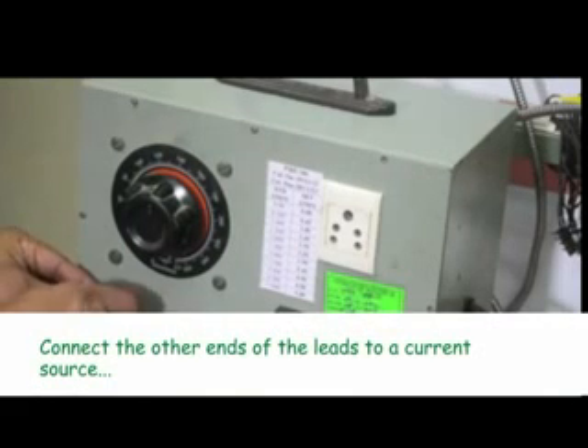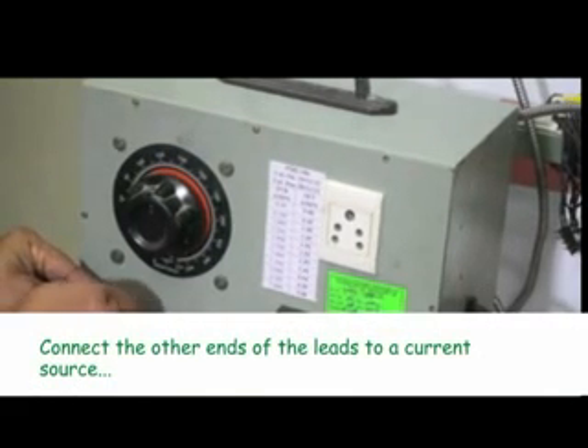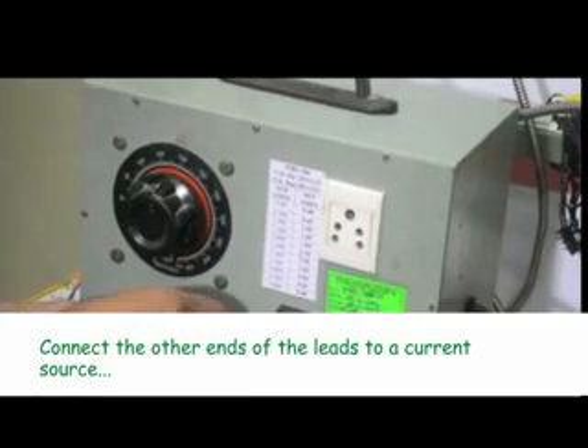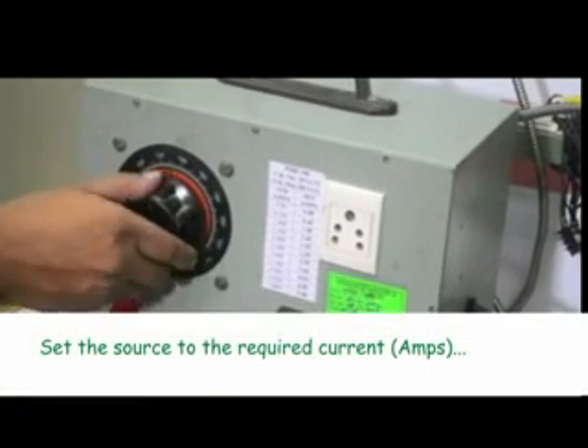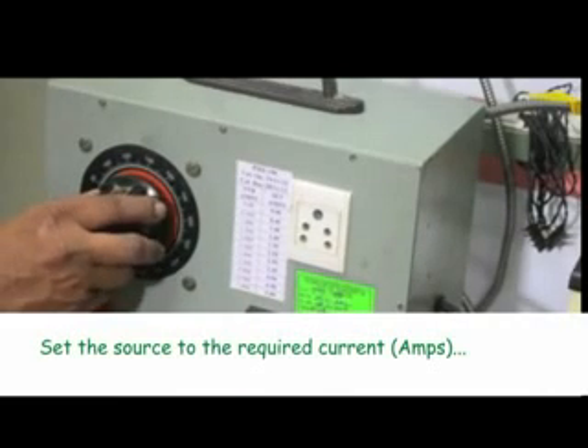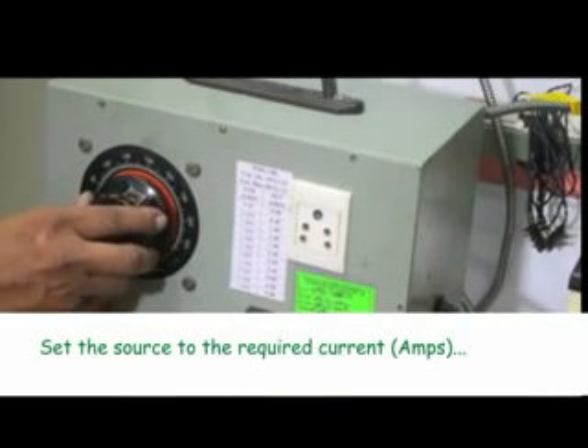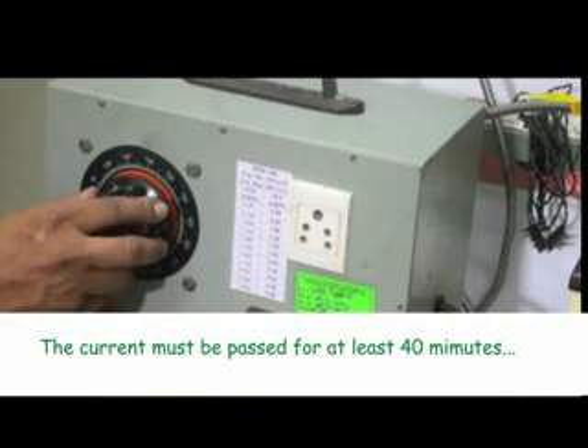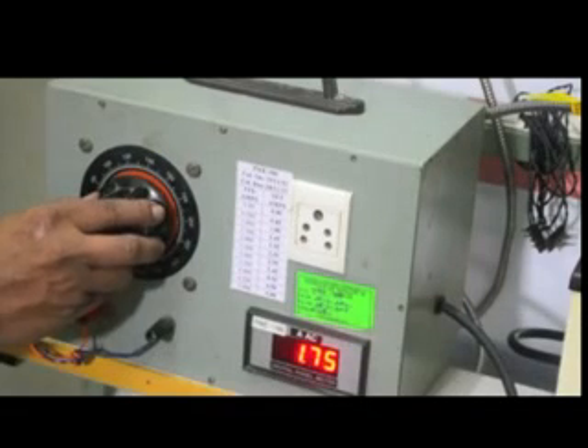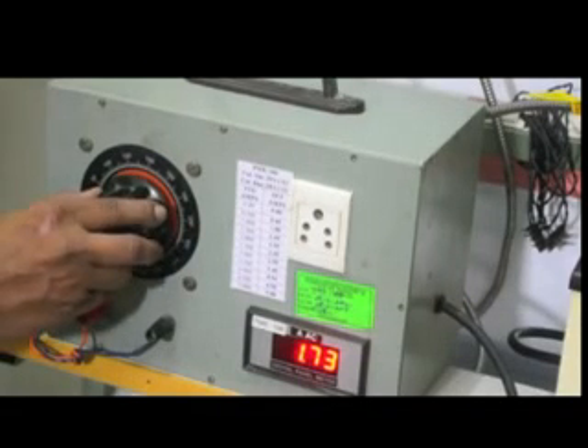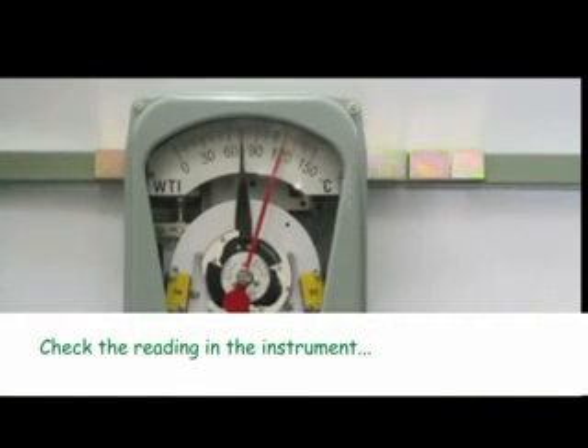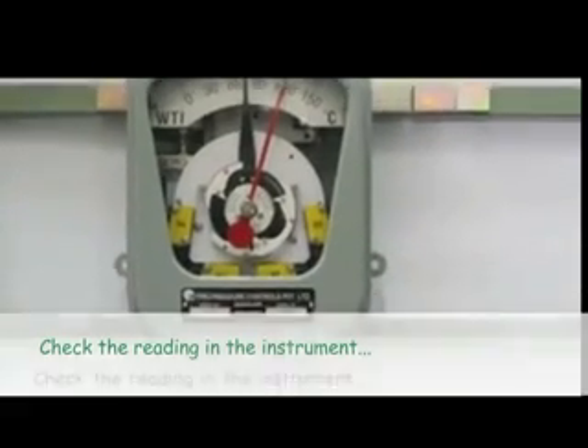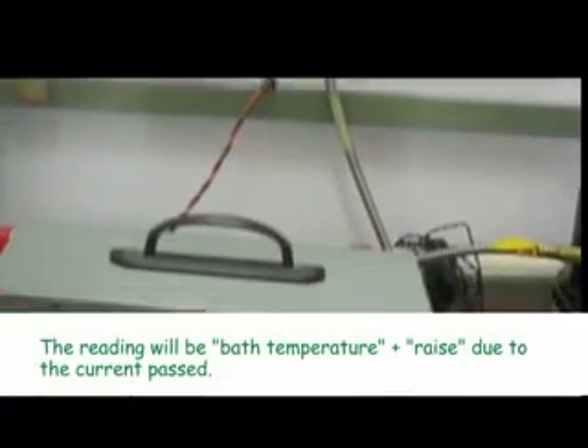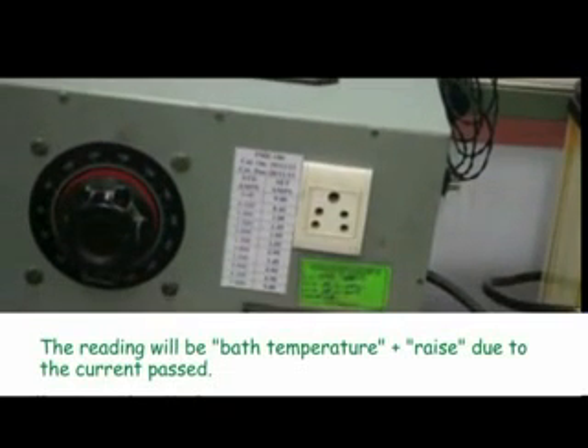Connect the other ends of the leads to a current source. Set the source to the required current in amps. The current must be passed for at least 40 minutes. After 40 minutes, check the reading in the instrument. The reading will be the bath temperature plus the rise due to the current passed.